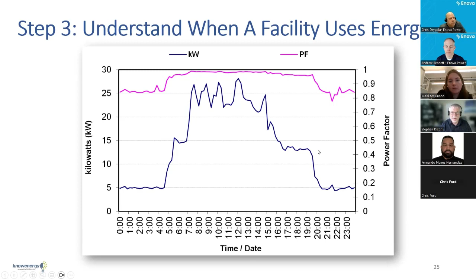So these profiles are really, really insightful. Even without the power factor information, and maybe not even electricity, we're starting to gather hourly gas data for buildings. This building had 4 boilers that were all basically the same size. They were supposed to be sequenced and controlled, but what we discovered was there were times when all 4 boilers were slamming on and off.